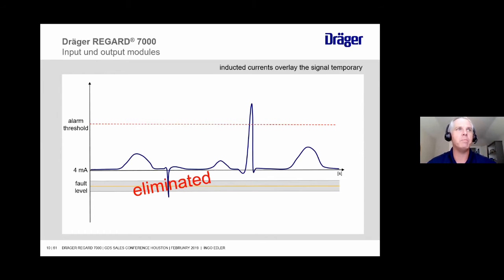Because let's say, for example, that these milliamp runs could be pretty long, and it's just a milliamp signal traveling from the transmitter to the controller. So if you have a big piece of equipment kick on, or something happens that causes some electrical interference, you could cause a false alarm or not actually get to the fault set point that you need in order for the controller to say, I'm actually in fault. So we put a little deadband around it to make sure that the fault signal is actually hit.